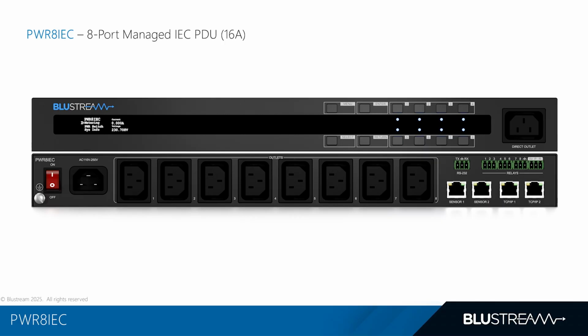Where this unit really expands its capability is environmental and security awareness. It includes dual sensor RJ45 ports that accept multi-format third-party sensors. So those can be temperature, humidity, air pressure, door tilt, PIR, and more. For each outlet, you can define what should happen when a threshold is crossed. Either that's no action, power on, power off, or restart. And you choose the logic. So that's no trigger, a minimum threshold or maximum threshold, or min or max, perfect for automating cooling fans, shedding non-critical loads, or rebooting a misbehaving device when environmental conditions stabilize.